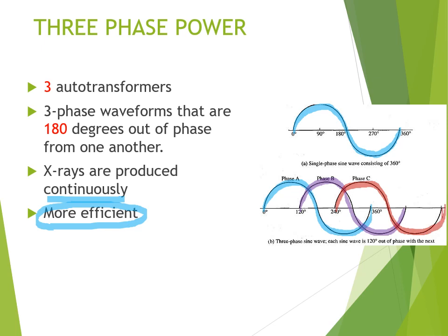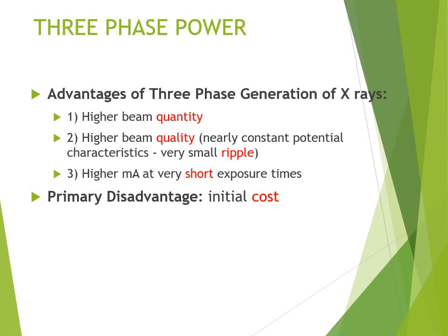And we're going to produce, we're going to then rectify those negative pulses and get a total of 6 pulses going across in a positive direction. So the advantages of 3-phase generation of power is higher beam quantity, higher beam quality, which is nearly constant potential, very small ripple. We're going to have higher MA at very short exposure times, and the initial cost is going to be a big disadvantage.